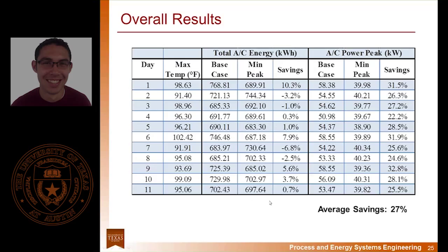This highlights the benefits of the centralized controller to leverage the thermal mass of each house, which not only resulted in some cut to the total AC energy, but a significant cut to the peak power. The centralized controller uses thermostat control to shift when each house is using free cooling, staggering when units turn on or consume a lot of energy, leveling the load a little bit. We saw in that earlier graph how the load was spread out and flattened, which is a lot easier for utilities to deal with than finding additional capacity or buying off the electricity market during peak hours.